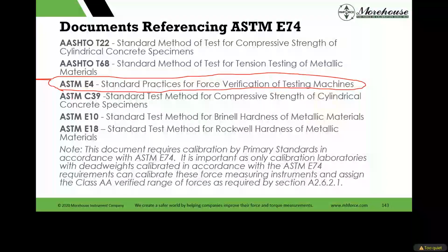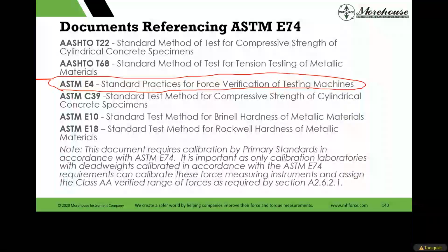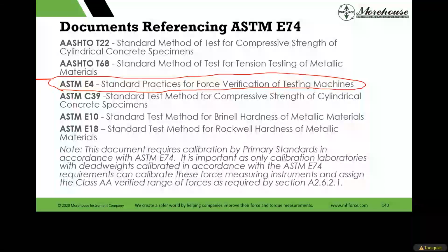Like marking equipment already earlier, how you're using it. If you're using any S-beams, are you telling the lab how you're calibrating them? If you're pulling out that top adapter, what I call the integral threaded adapter, you're going to get much different results that are going to put your testing machines out of tolerance, and you'll be adjusting something that's actually good. Yeah, ASTM E10 was the Brinell hardness.